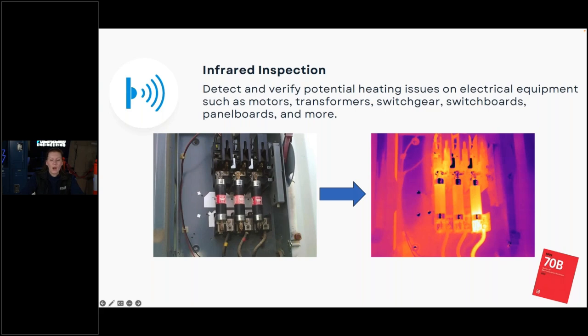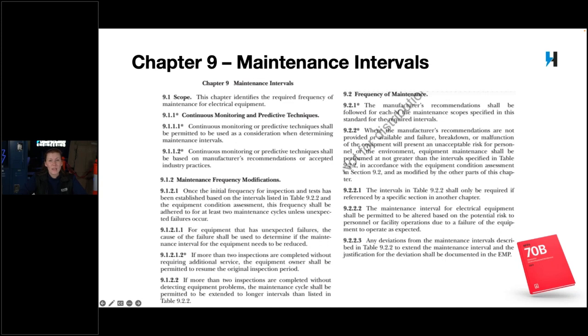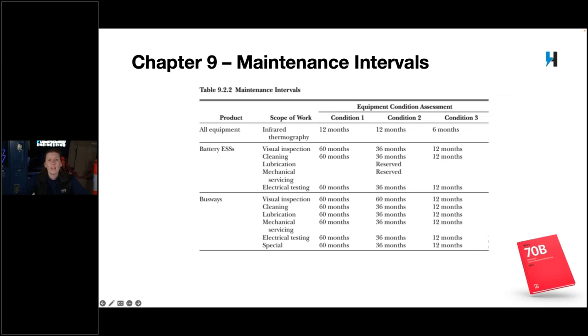A lot of people ask, how often do you need to do these scans? Well, we can go to chapter 9 in the 70B, maintenance intervals, and a lot of people want a straight up answer - every year. The vast majority of equipment, I would hope we can just do once a year - that's the minimum requirement, annual. But it depends on the current condition of that equipment. So the maintenance frequency modifications in 9.2 need to be adjusted according to the different conditions. You can go and read through this or ask questions later if you'd like. I'm just going to jump to that table that's referenced.